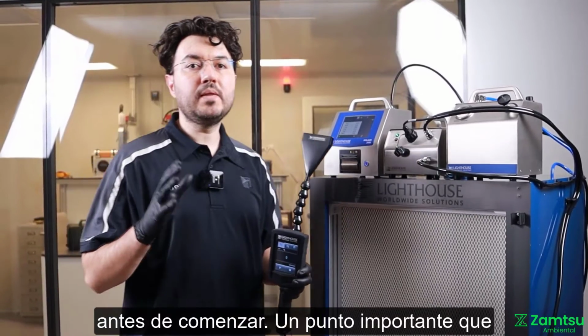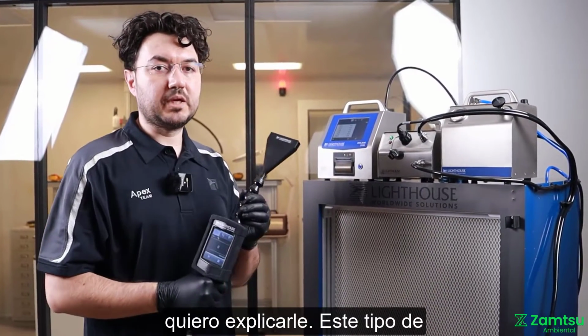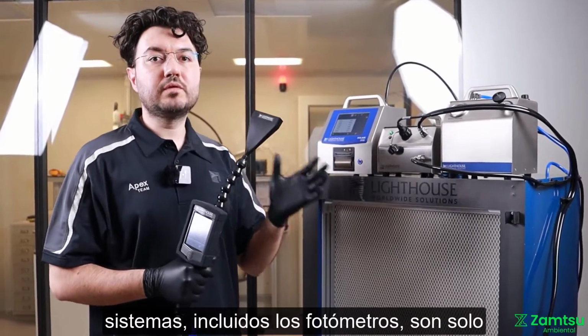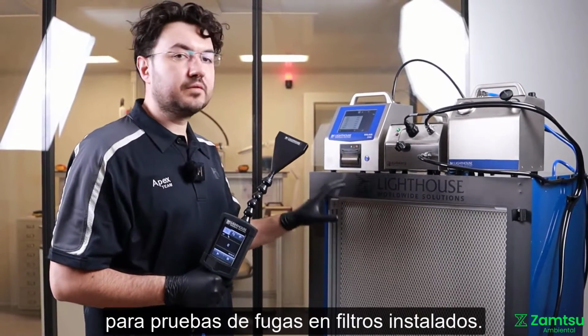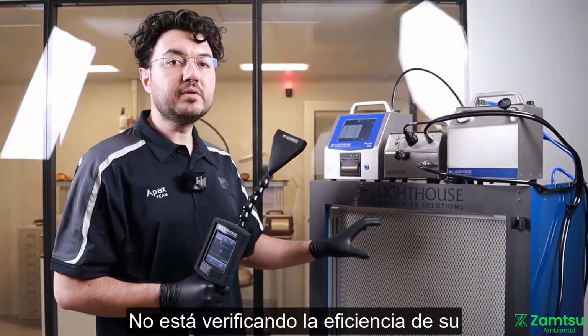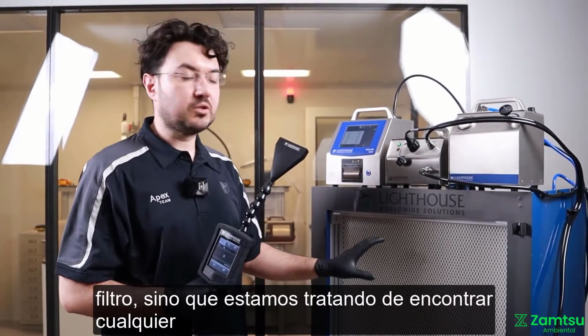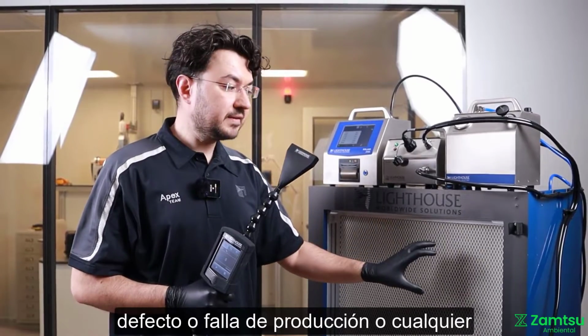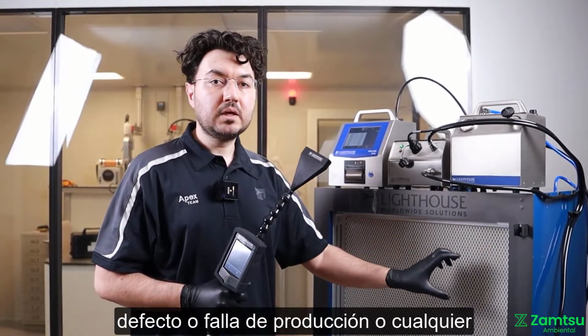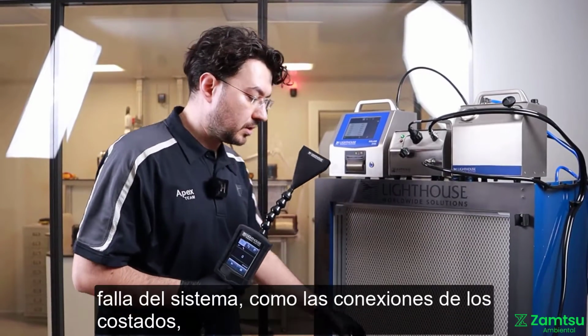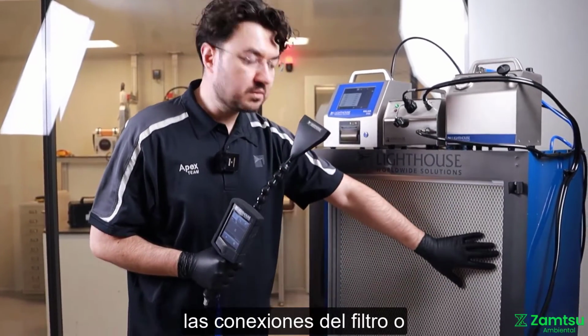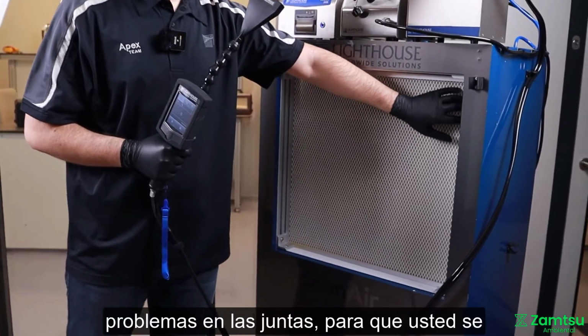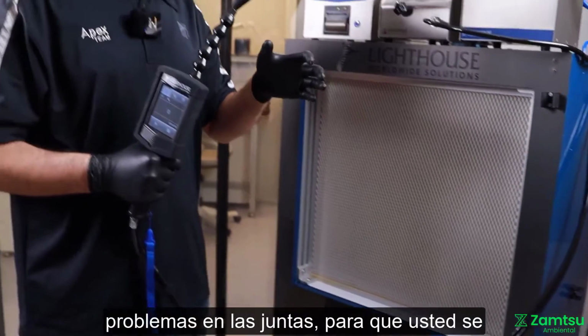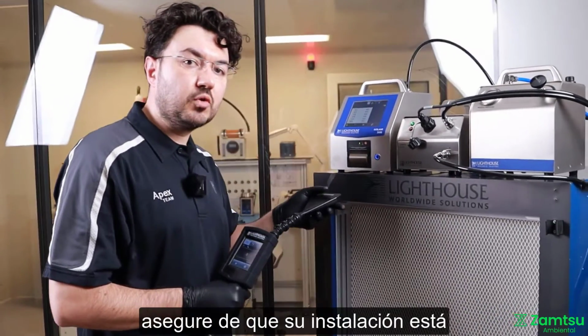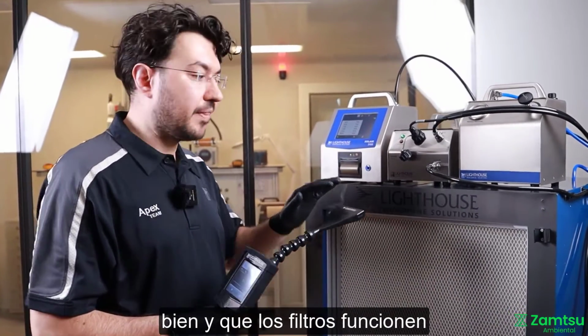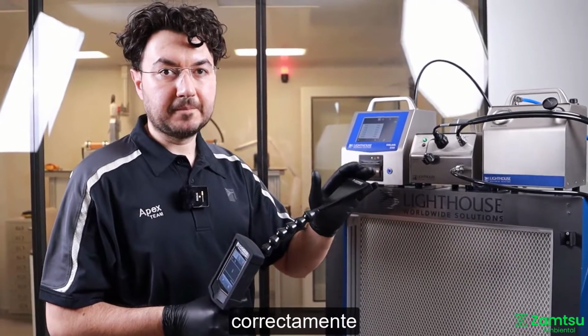Before we start, one important point that I want to explain to you. These kinds of systems, including photometers, are only for installed filter leakage testing. You are not verifying any efficiency of your filter, but you are trying to find any defect or any production failure or any system failure like the side connections, filter media connections, or the gasket media issues, so that you will make sure that your installation is okay and the filter is performing correctly.